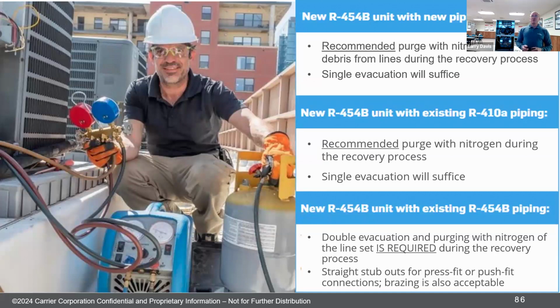On a new 454B with new piping, you do a purge with nitrogen, you're doing your pressure test, and the single evacuation is fine. If it's a new 454B system that you took out an old 410A system, you've recovered that 410A refrigerant, you just do a single purge and a single leak test and then a single evacuation, and that should be fine. If you're changing out a 454B system or component with another 454B, in other words, if that system already had 454B refrigerant in it, you're doing a double evacuation.